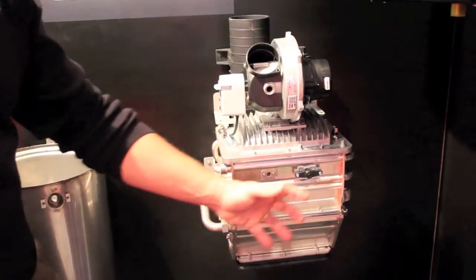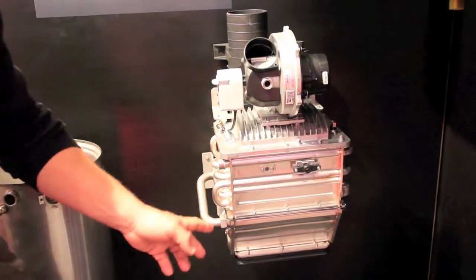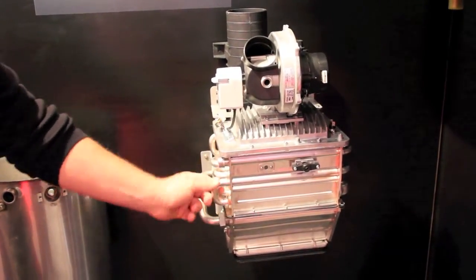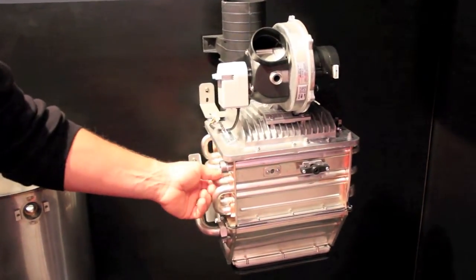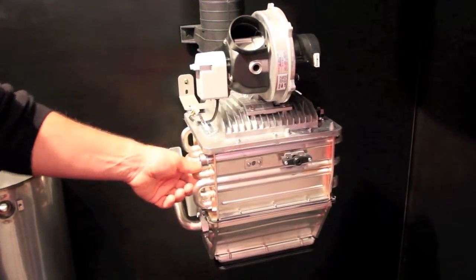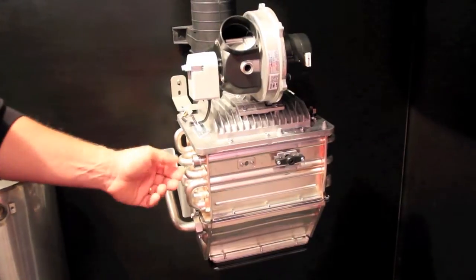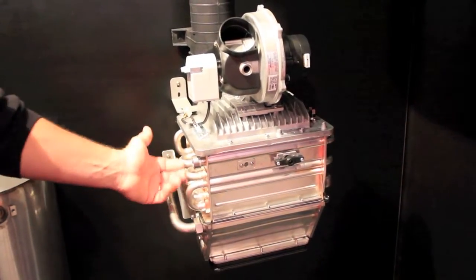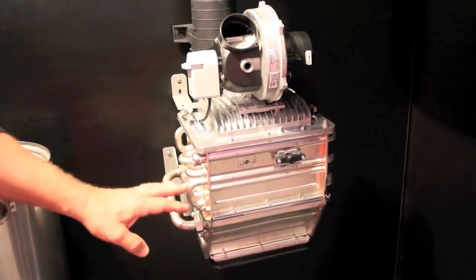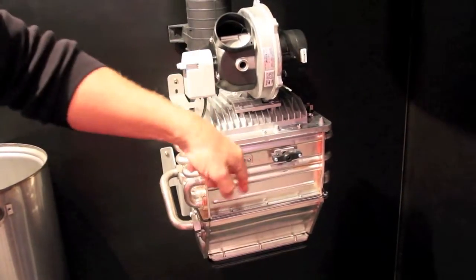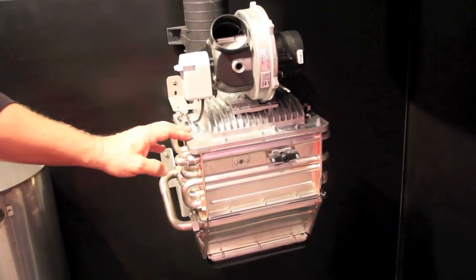This is a closer look at the heat exchanger taken away from the cabinet, as you can see. But you can see that the tube diameters are a lot larger than what you would see with other tankless units, which will help long term as far as its ability for better flow characteristics, better heat transfer. So we have our top section here, and we downfire, and it's a rectangular burner that we fire.